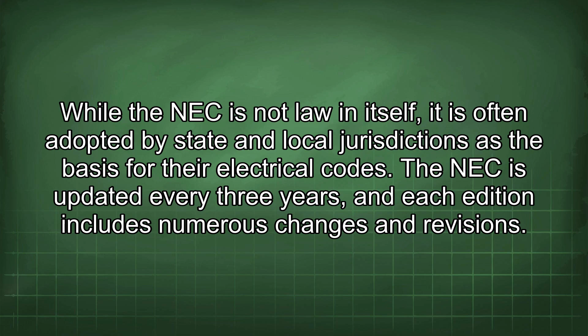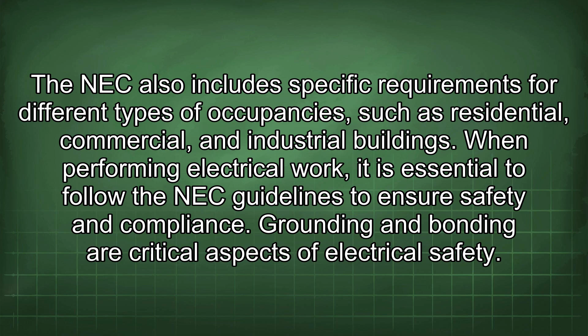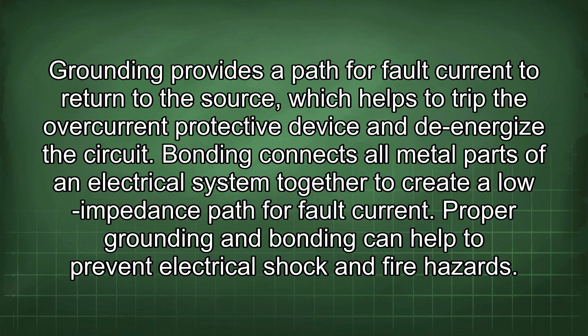Some key areas covered by the NEC include wiring methods, overcurrent protection, grounding and bonding, and equipment installation. The NEC also includes specific requirements for different types of occupancies, such as residential, commercial, and industrial buildings. When performing electrical work, it is essential to follow the NEC guidelines to ensure safety and compliance. Grounding and bonding are critical aspects of electrical safety. Grounding provides a path for fault current to return to the source, which helps to trip the overcurrent protective device and to de-energize the circuit. Bonding connects all metal parts of an electrical system together to create a low impedance path for fault current. Proper grounding and bonding can help to prevent electrical shock and fire hazards.